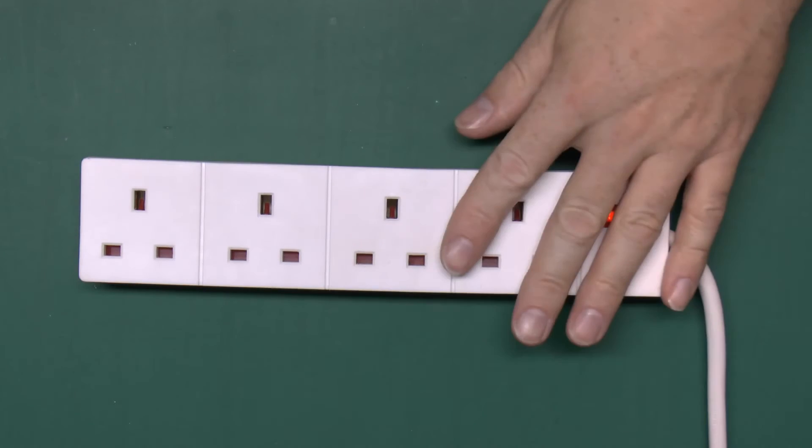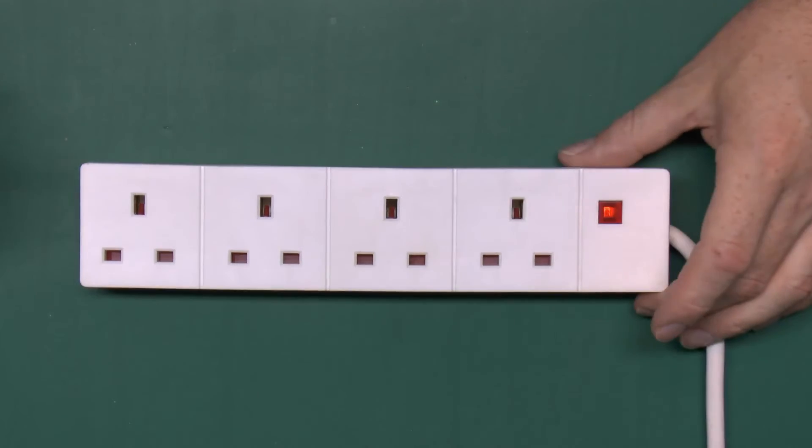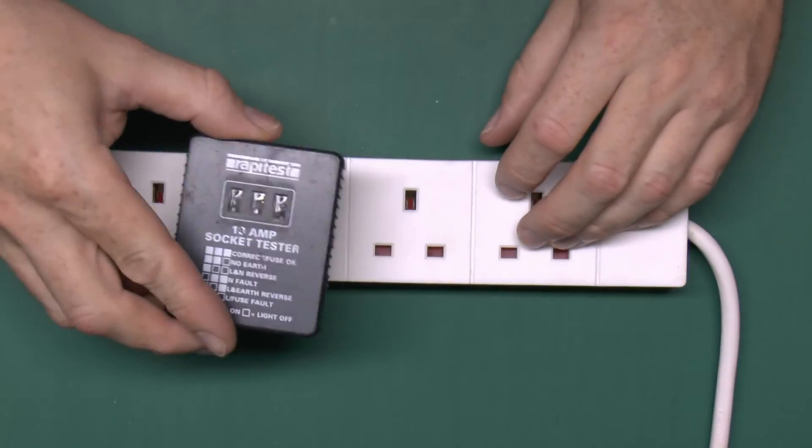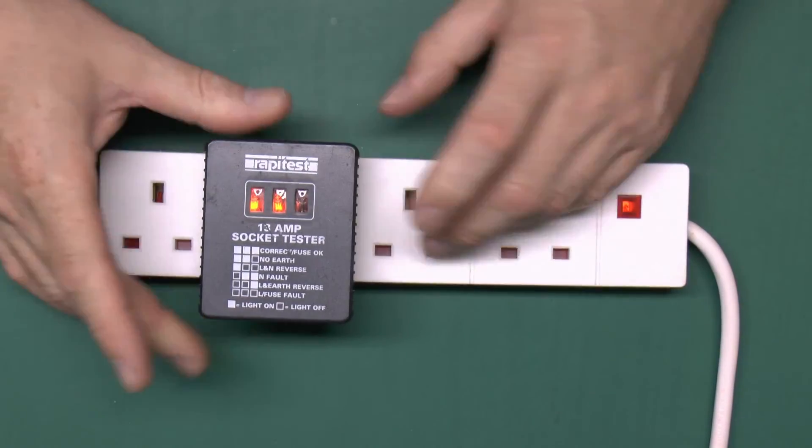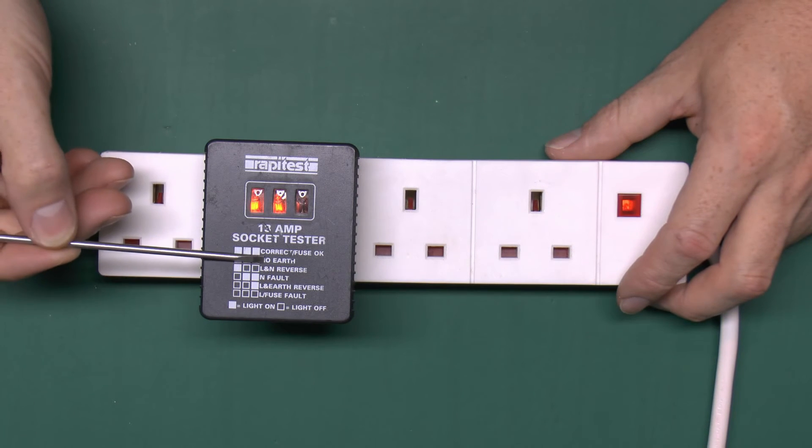Now I've just unplugged this from the mains and plugged it into an isolating transformer, which obviously the indicator here still illuminates, so we've still got power there, so let's see what this thing tells us now. Well there we go, we've only got two lights on, which according to the legend here means there's no earth.